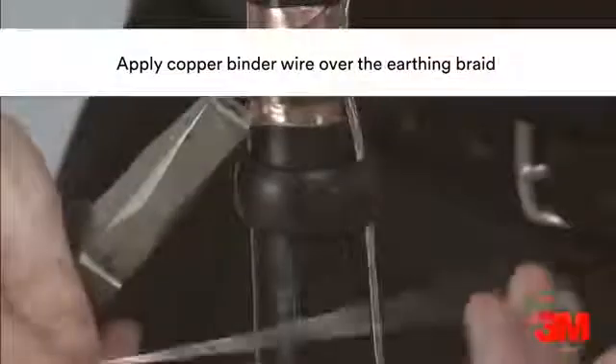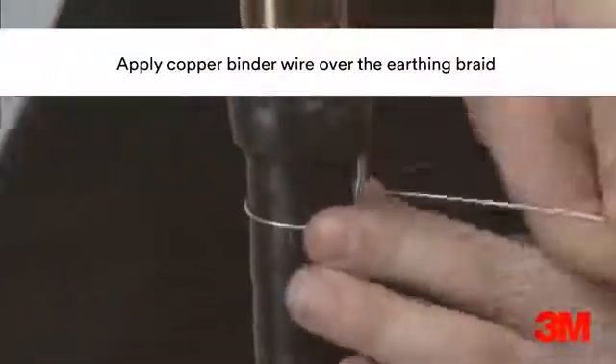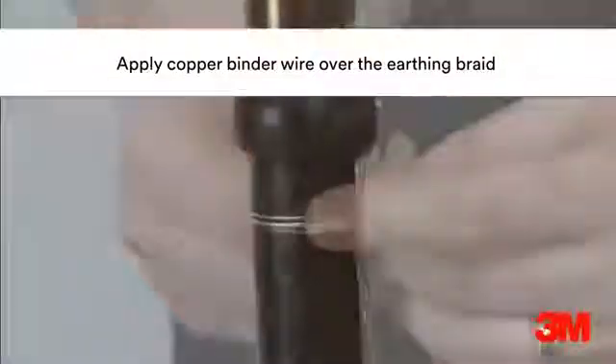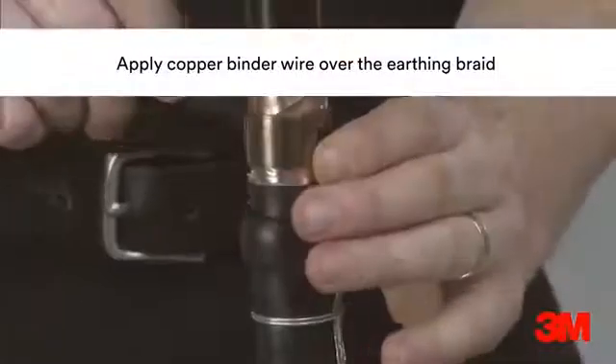To install, the earth braid is positioned and fixed in place with a constant force spring. A layer of Scotchfil 5313 mastic is applied around the cable as a bedding, before the braid is pushed into the mastic and secured by a copper binder.